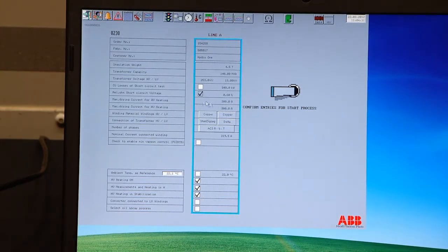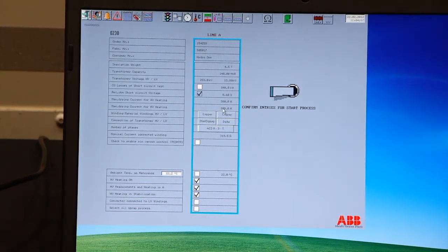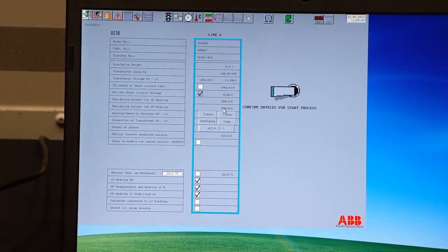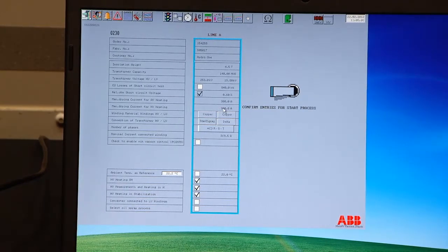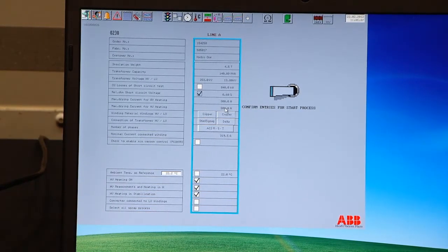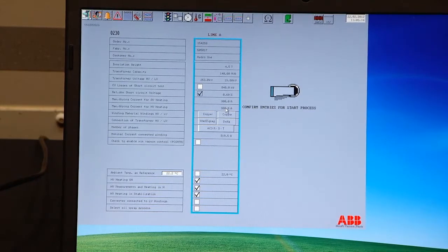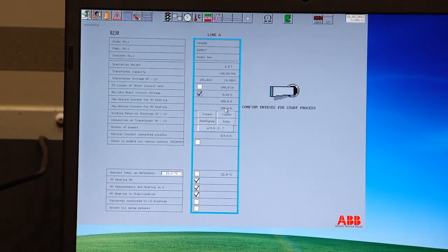And there you have 2 options for average heating: when you're heating both high voltage and low voltage winding, or you have an option to take only the high voltage winding when you're heating only one side of the transformer. The maximum, yes. Full winding. You can be a little bit conservative here. You don't have any oil cooling, you don't have any cooling effect at all. Still, this is only a safety factor. So take 80-90% of the maximum that you can expect.